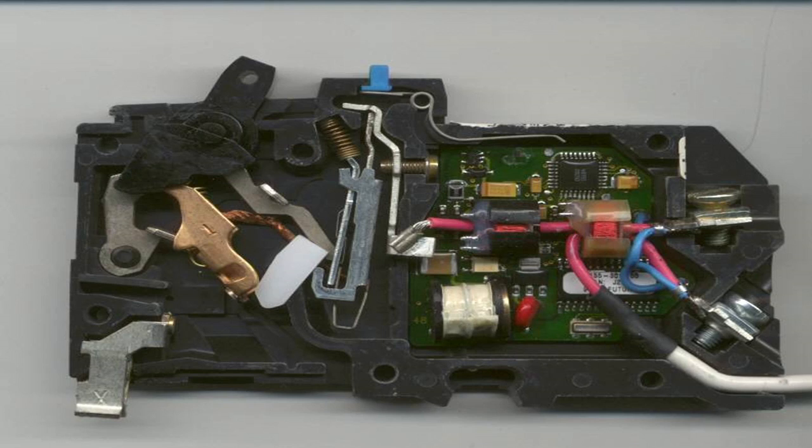Now, let me just close up because I'm afraid I'm going to forget this. All my breakers are dual rated, GFCIs and AFCIs, and all my two-pole breakers are GFCIs. Oh, there's another one: I have a single-pole breaker, actually a violation of code right now, that's not GFCI protected and not AFCI protected, which handles the lights in my garage. Because I have the T5 light fixtures.